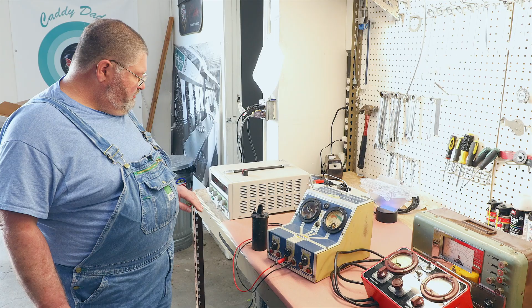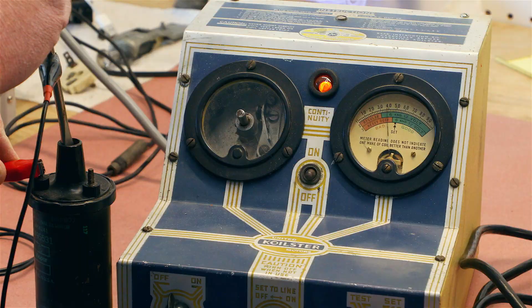So we're just going to show you the basic function. The first test here is continuity, and we're going to check that the primary has continuity, and we get our indicator light to come on. Then we have to get a screwdriver here to reach down and check continuity to the secondary, and it's also good.